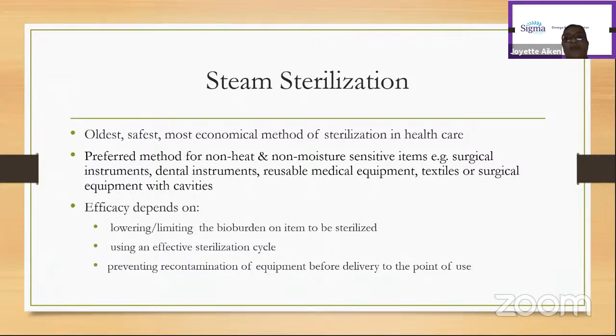And of course, they come in various sizes. You have large ones that take up half of a room, and you have small portable autoclaves. And there are different types of autoclaves. They have different mechanisms of action. But the general thing about steam sterilization and autoclaves is that their efficiency depends, one, on limiting the bioburden on the item to be sterilized. And that is key. We mentioned that already.